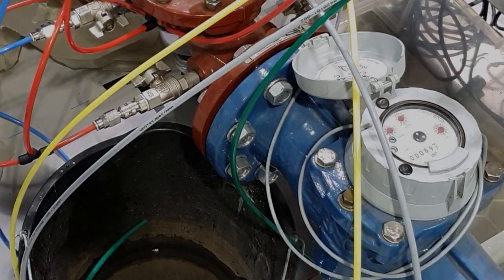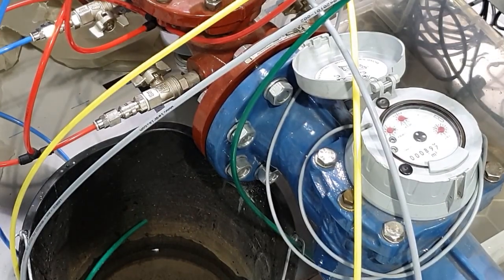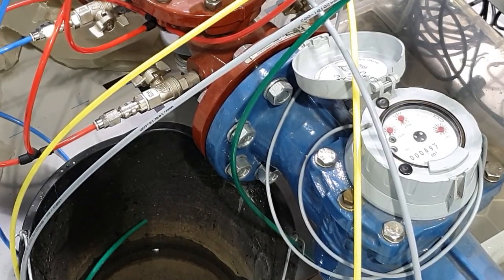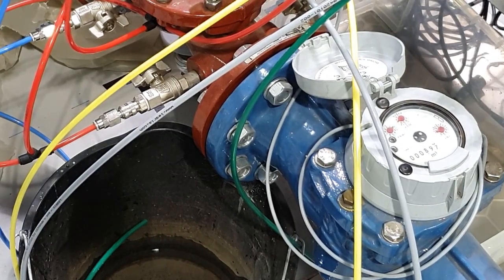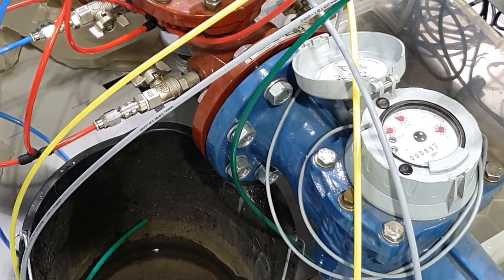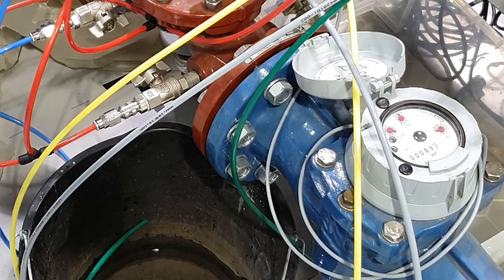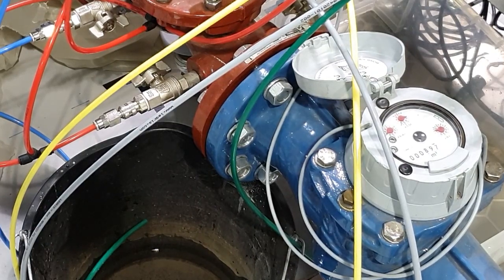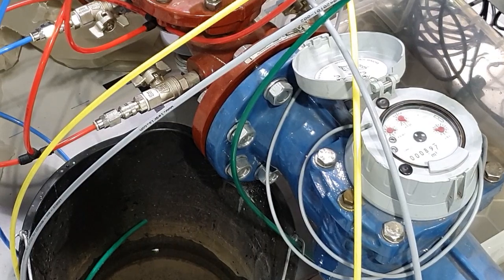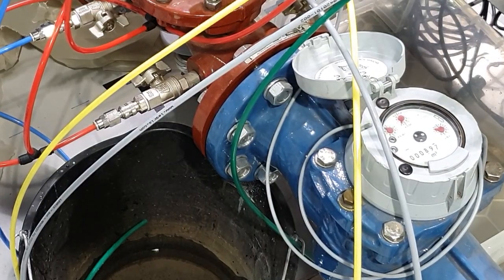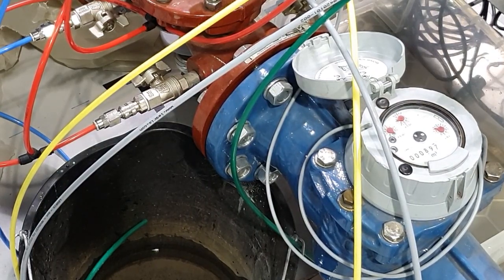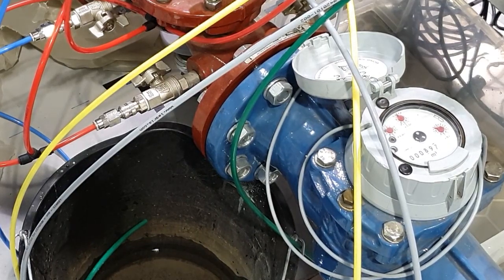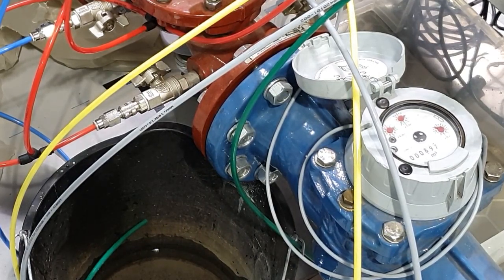Pegasus has a unique feature in the market, which allows it to act as a bypass between the hydraulic pilot and the upper chamber of any PRV, making the water to circulate directly through it. It is thanks to this characteristic that Pegasus is able to vent the remaining volume of water that is always in the upper chamber of the valves into the atmosphere, as you can see in the video.